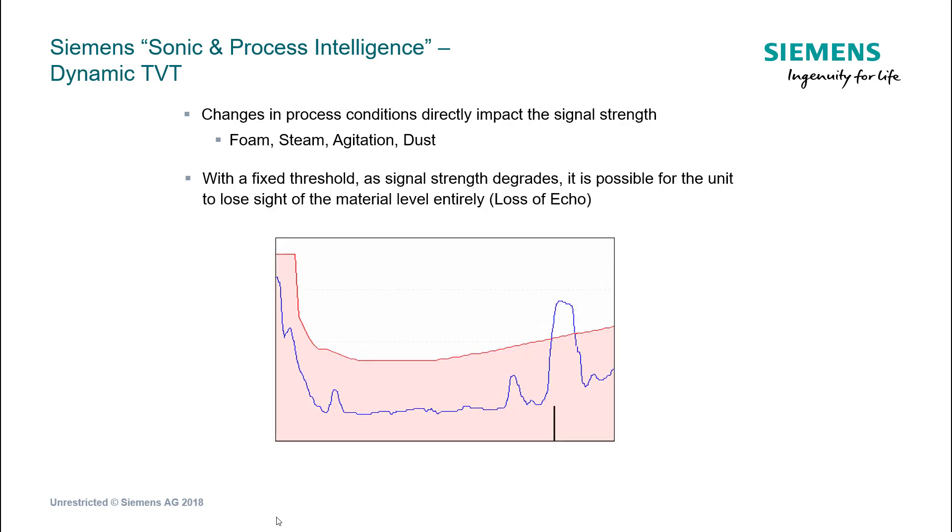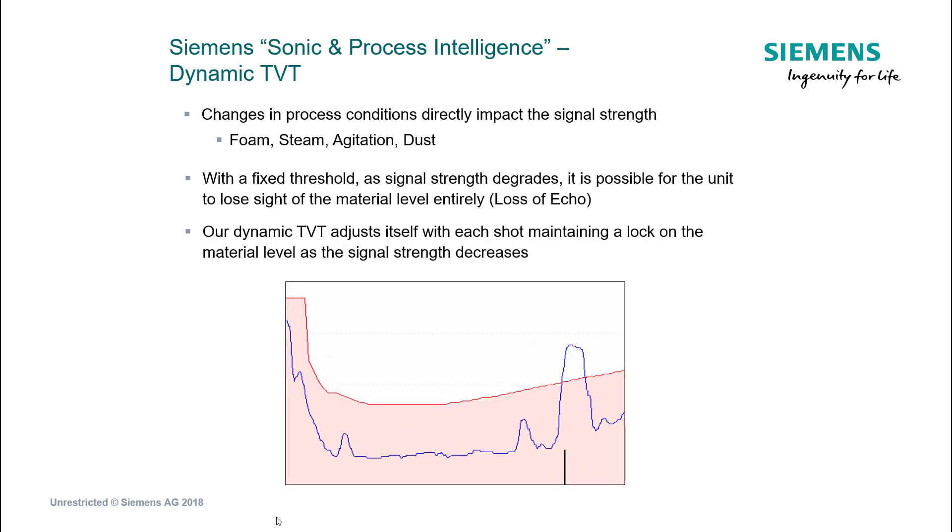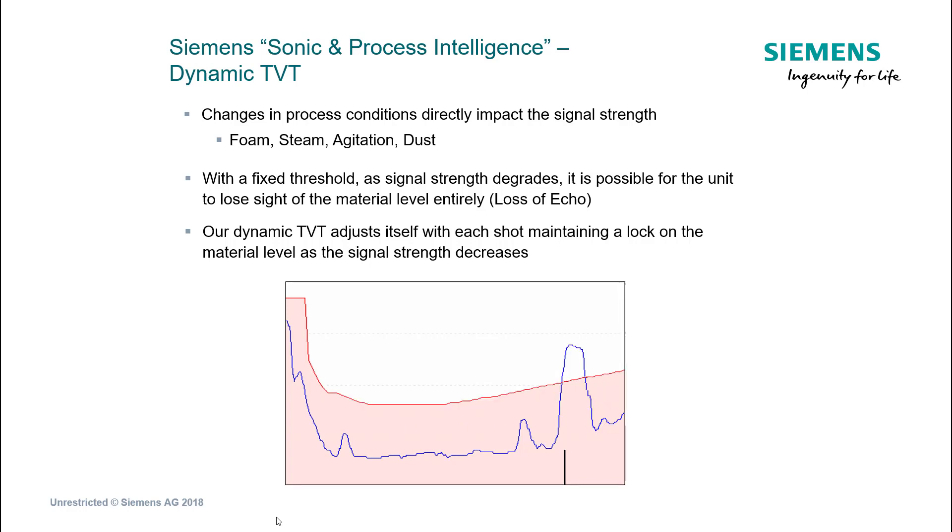If our red line is fixed then we have a problem with our signal going below that red line. It's no longer analyzed as an echo because we've told it anything below the red line to ignore. The red line needs to be dynamic and it moves with the change in process conditions in your vessel. If you don't have that, prime examples like condensation, build up on the face, and foam will attenuate the signal and you'll lose the signal altogether.